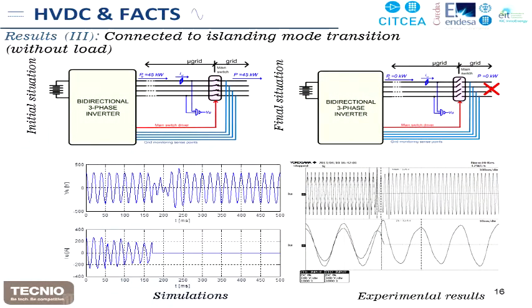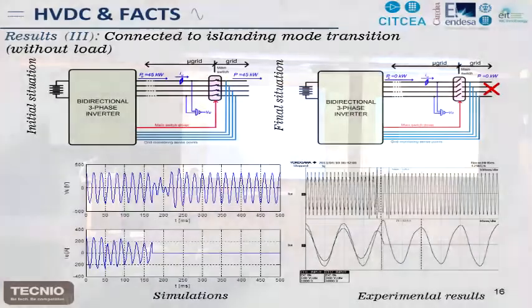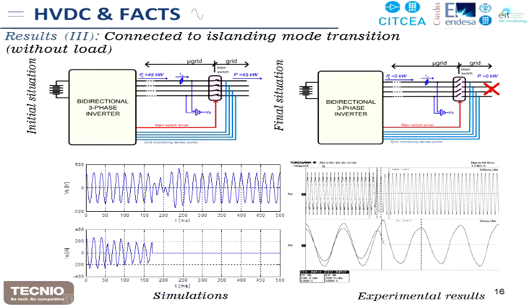Okay, so if we move on to the transitions, as I have said before, I only want to show the transitions that go from grid-connected mode to island mode. Why not the other ones? Because when you are going from island mode, you have a more controllable situation, because the system can be synchronized with the grid and then make the reconnection. So if there is one transition that has to be treated with more consideration, it is the transition that implies being connected to the grid at the start point, and then starting to operate isolated from the grid.